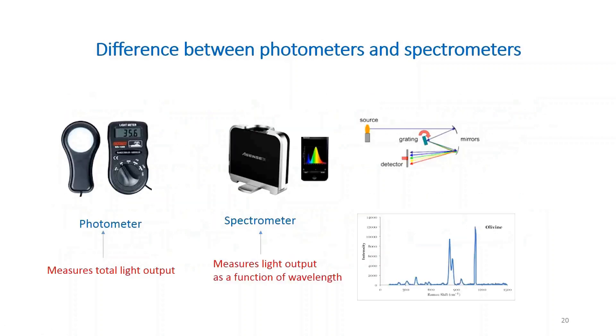A photometer measures total light output (e.g., in lumens) without distinguishing between wavelengths. A spectrometer, such as the Lighting Passport, not only measures light output but also resolves it at each wavelength using a diffraction grating that separates wavelengths onto a detector. This provides a full spectral understanding of the light source.